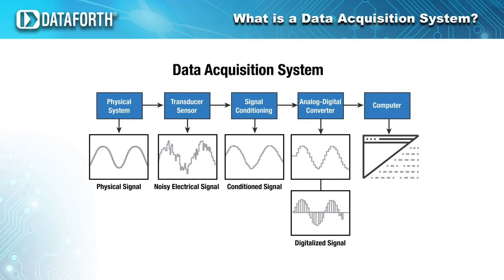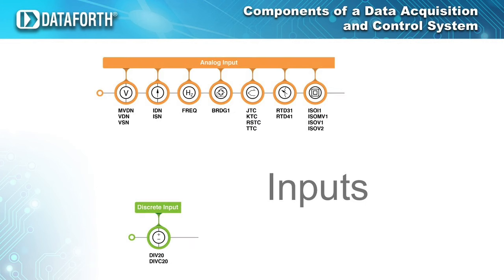One other item to pay attention to in the real world is that every signal usually carries some kind of noise. A noisy signal from a sensor is not clean enough to immediately convert into the digital world. Luckily, there's a function of signal conditioning to minimize the impact of errors caused by wires and the imperfection of the sensors. In some cases, part of the signal conditioning function is also isolating the high voltage circuitry from the low voltage side where the host computer resides. The first link in acquiring real-world signals is connecting a sensor to what is called an input module.